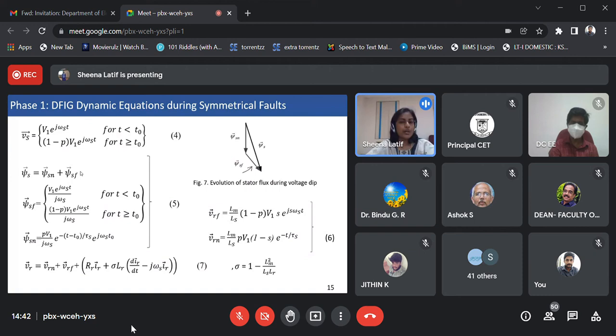Dynamic equations of DFIG during symmetrical fault conditions. If t0 is the instant at which the fault occurs, then the stator voltage magnitude now reduces to (1 minus p) times V1, a phasor rotating at synchronous speed. In the case of the stator flux, in addition to the steady state or forced component, an additional natural flux component also occurs in order to avoid any discontinuity between the pre-dip and post-dip conditions. This homogeneous or natural component is an exponentially decaying component, and it is directly proportional to the depth of the voltage dip.